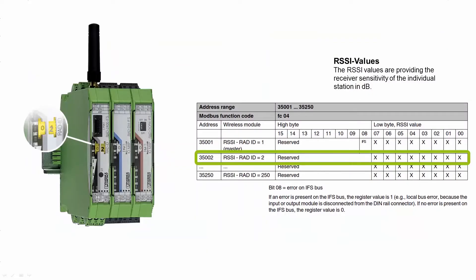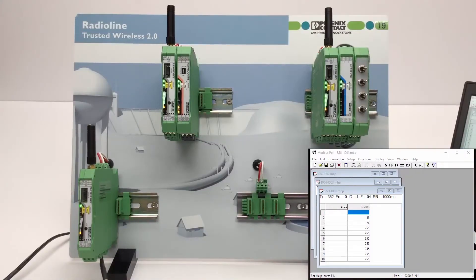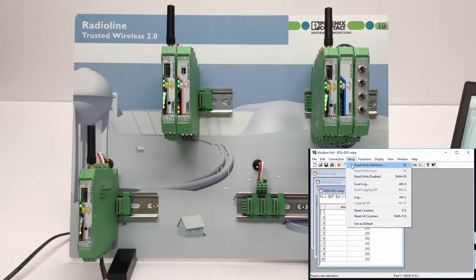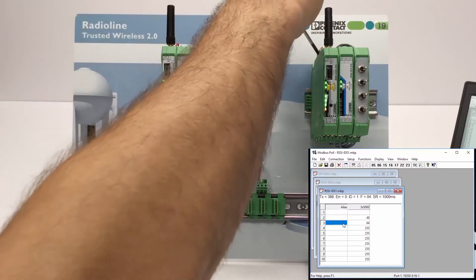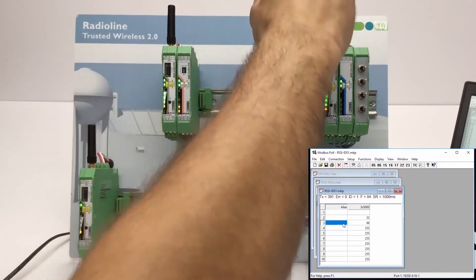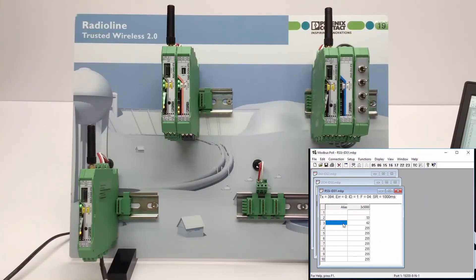The Modbus table also provides status and diagnostic parameters of the individual radio stations, such as the RSSI values, also known as signal strength of the respective radio stations. The RSSI values of all wireless modules in the network are stored in the address range 35001 to 35250. For example, to read out the signal strength of the radio station with RAD ID 02, register 35002 must be read. The register indicates the signal strength in dB. When a wireless station is disconnected from the network, the value 255 is displayed. This allows a Modbus controller to monitor the complete wireless network.